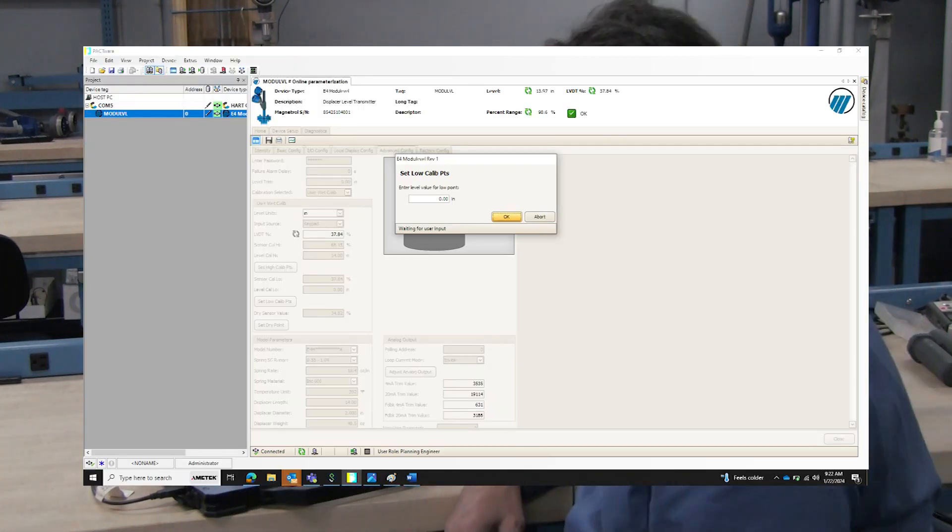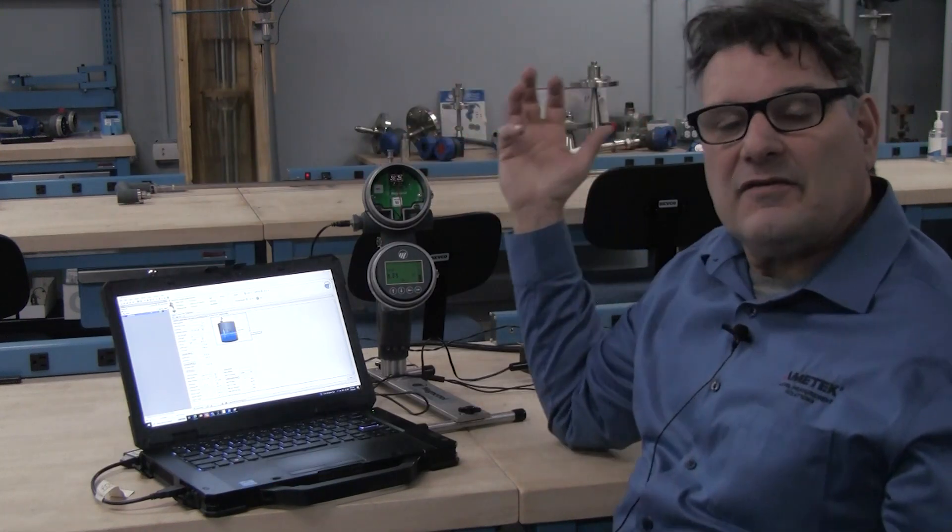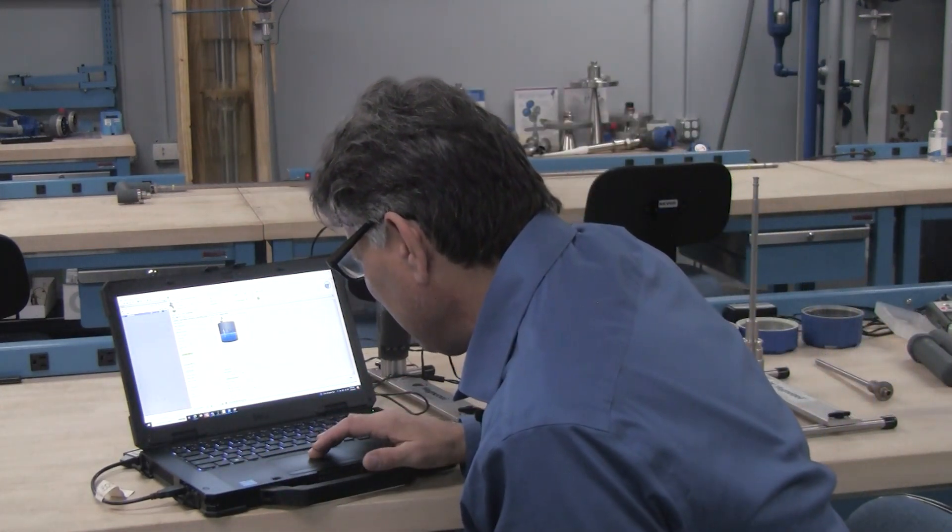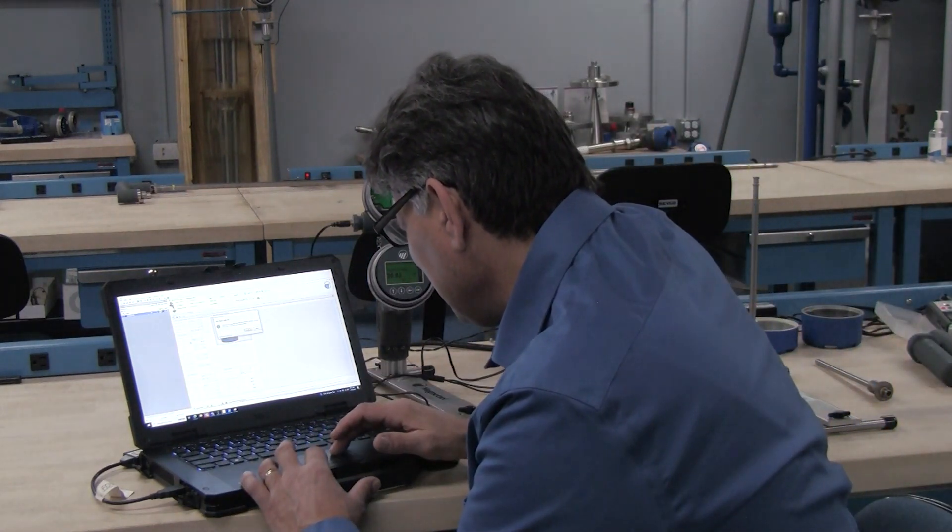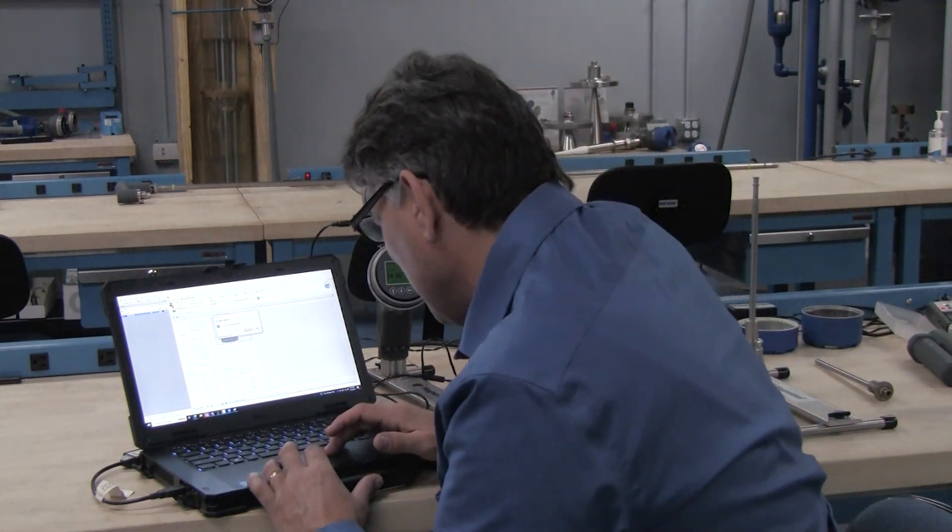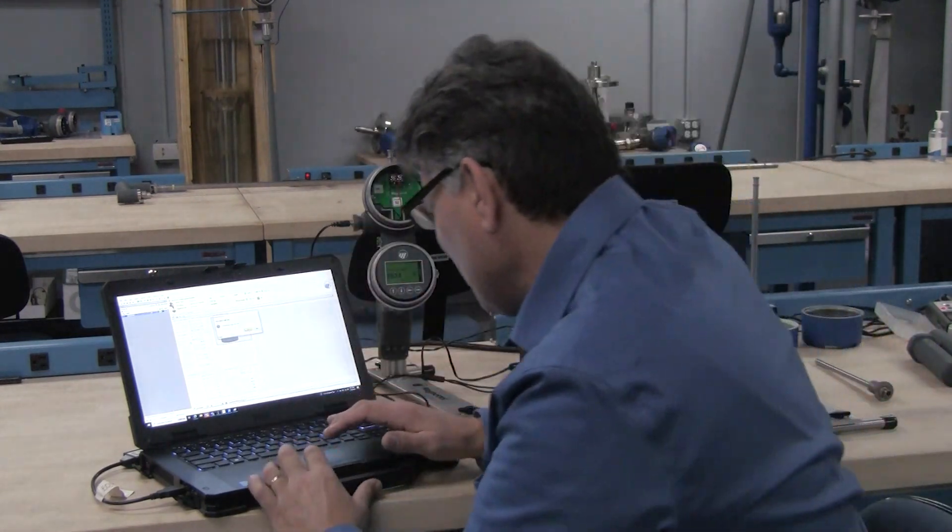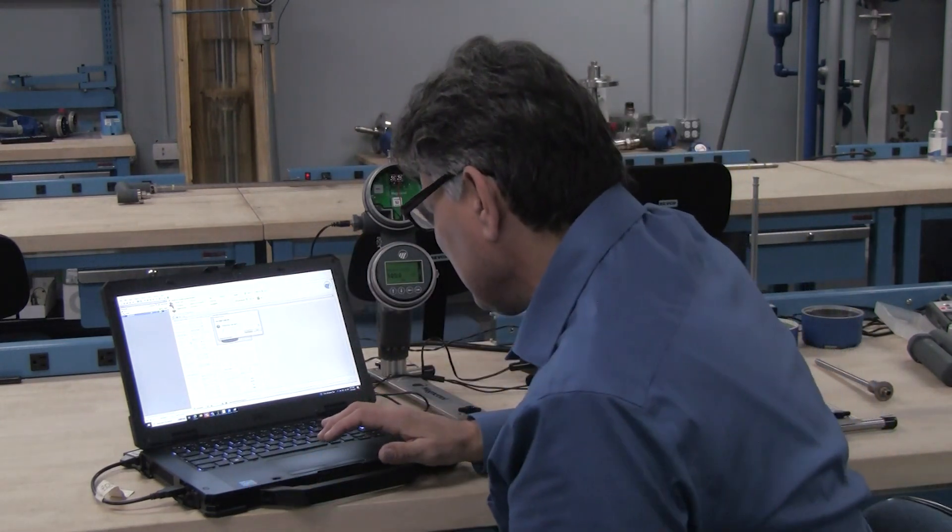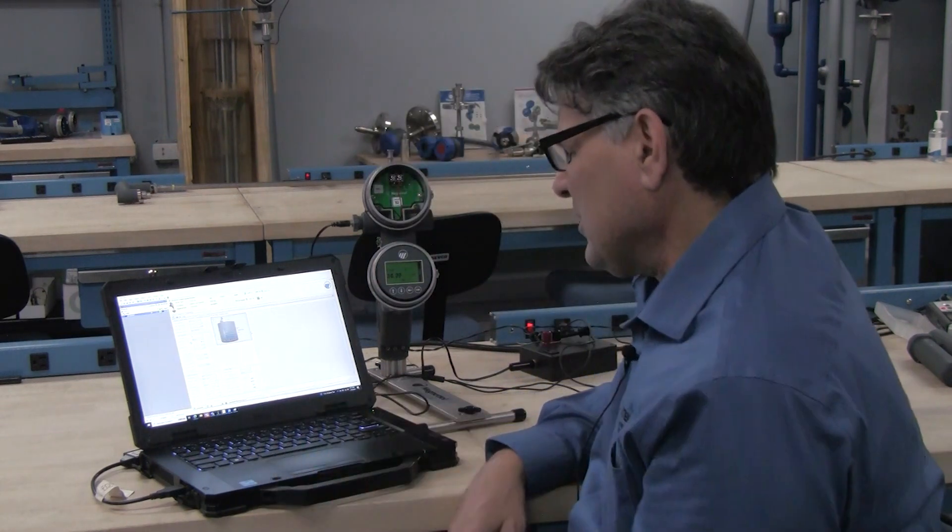Now I can lift this up simulating a high level or a higher level on the actual displacer. And now we'll go in and set my high point. And it'll ask me the same questions for the high point. And I'll go ahead and scroll through these. It gives me my percentage that the LVDT is at. I'm going to say yes.